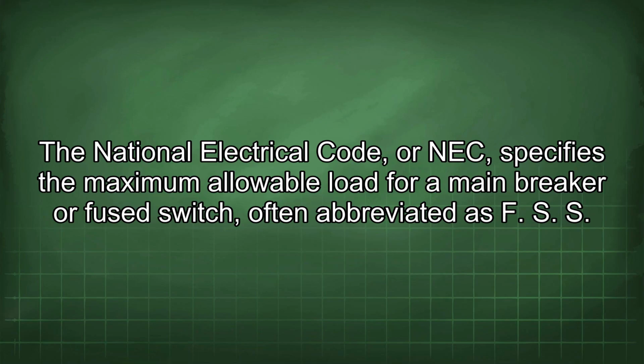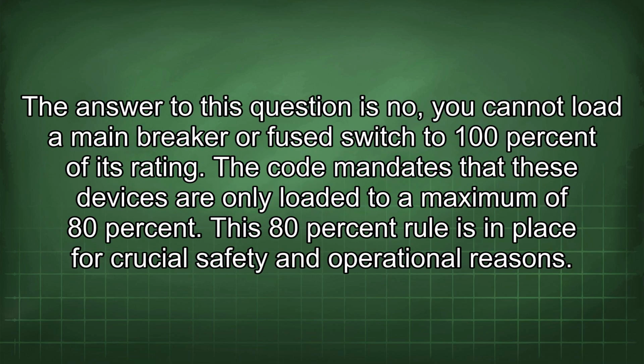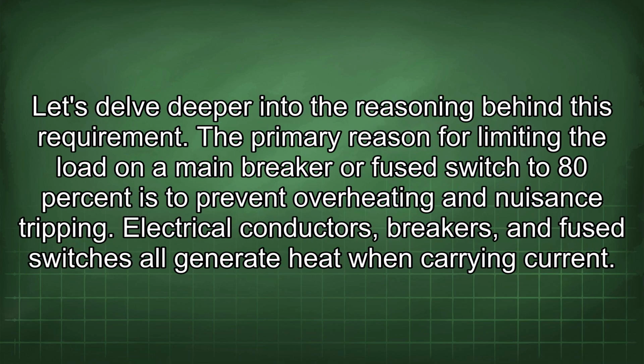The National Electrical Code, or NEC, specifies the maximum allowable load for a main breaker or fused switch, often abbreviated as FSS. The answer to this question is no. You cannot load a main breaker or fused switch to 100% of its rating. The code mandates that these devices are only loaded to a maximum of 80%. This 80% rule is in place for crucial safety and operational reasons. Let's delve deeper into the reasoning behind this requirement.